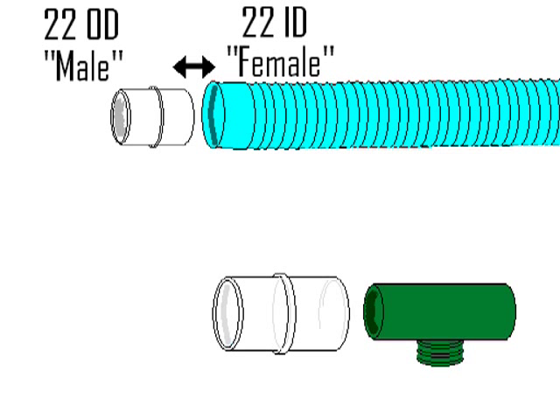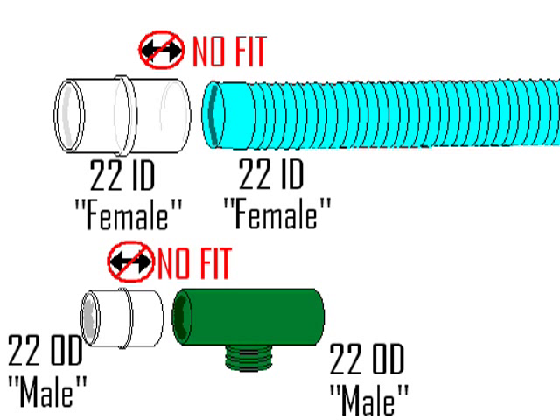Those are the things that fit: 22 OD male and 22 ID female, for obvious reasons. Two adapters of the same size will not fit together — such as 22 ID females not fitting together, nor do 22 OD males.